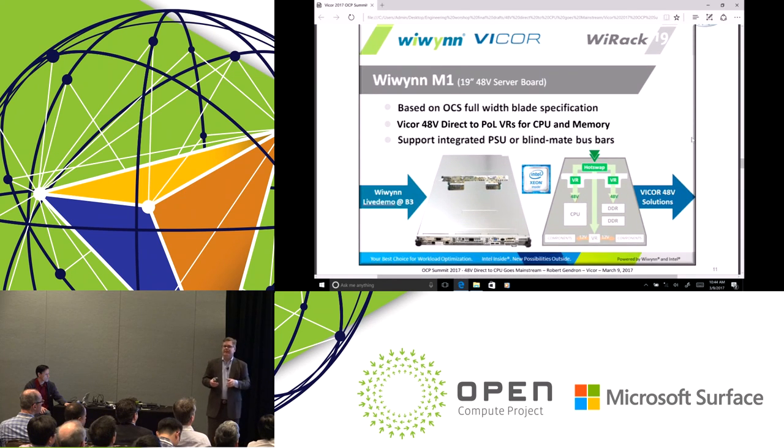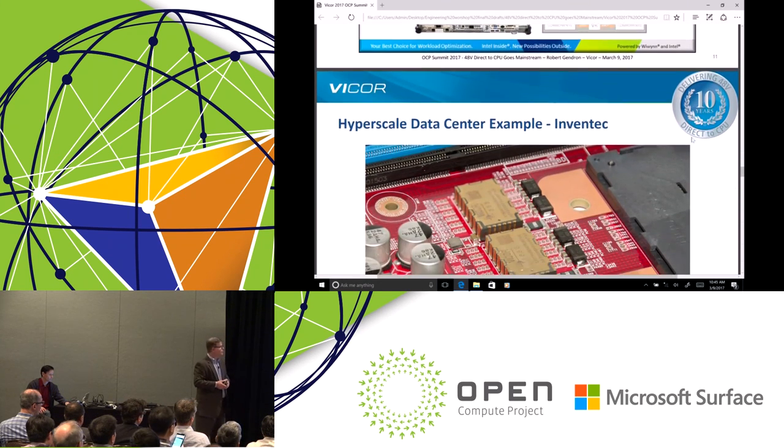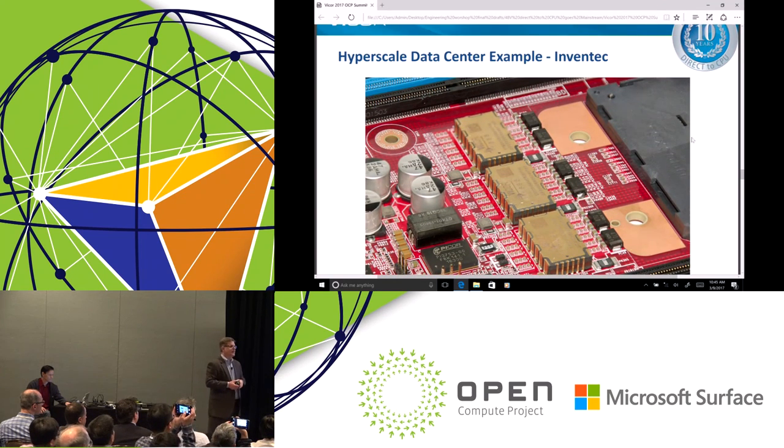Here are some examples of products that are out there or being released soon. Right here at the show, they announced yesterday an OCS compliant blade — if you look in their booth you'll see the implementation exactly as I showed: 48 volt direct to point of load for CPU, memory, and auxiliary rails. Another example is Inventec, who recently did an IBM P9 processor design. In that case the load is over 300 amps, requiring three of our VTMs in parallel supplying the load, with our PRM device sitting behind them.